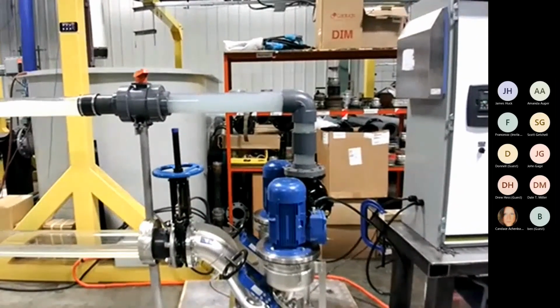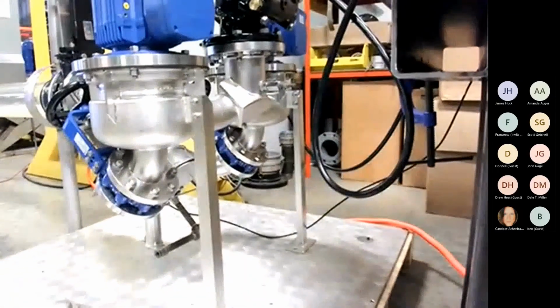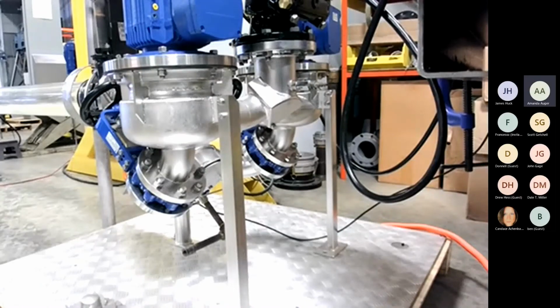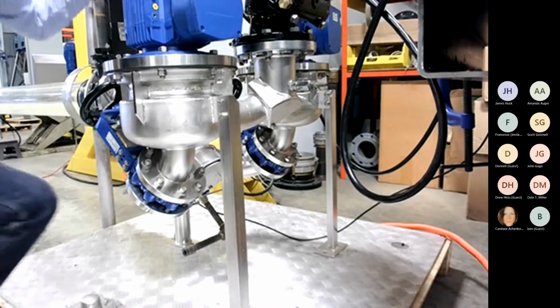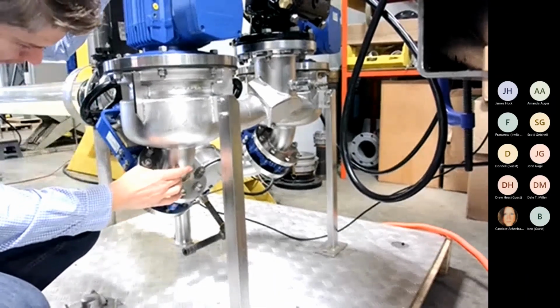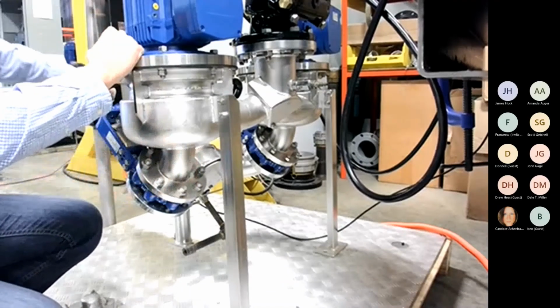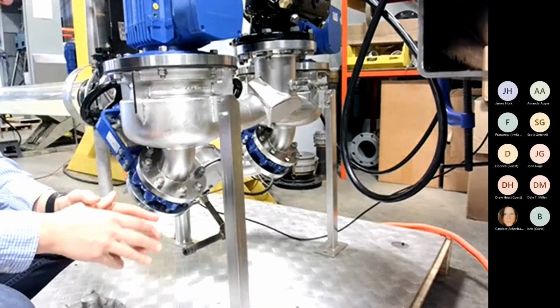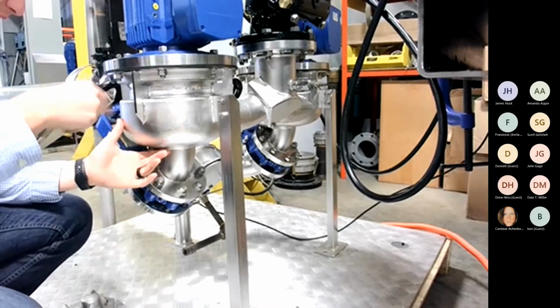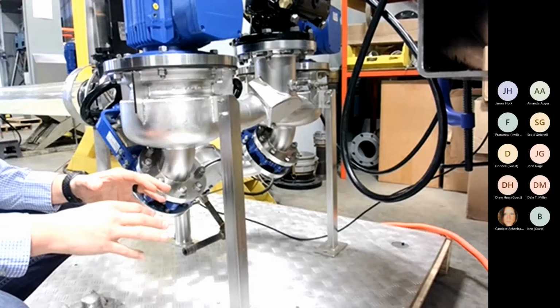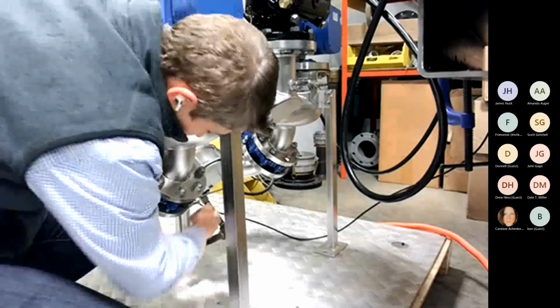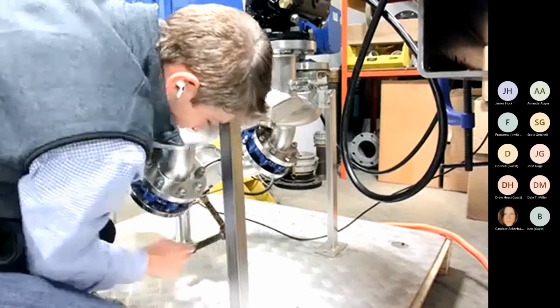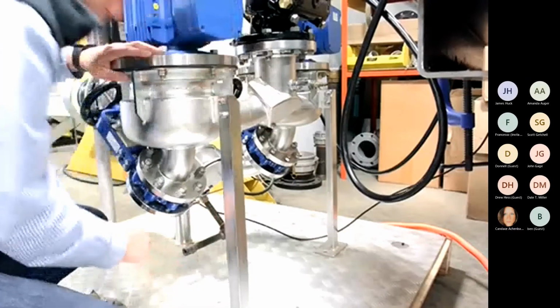Let me take you over here, camera down. I don't know if you guys can see. Yep, we can see it. You can see the bottom side here. So any large particles that come into this environment - what's nice is this branch valve here is sized for a 3-inch passable, and this is a 6-inch inlet. So anything smaller than 3 inches will come up into the pump and be shredded. Anything larger than that is going to sit down in the stone trap cleanout. Can you see this down here at the bottom? Here's a little handle, I have this little pipe on here out of the ball valve.